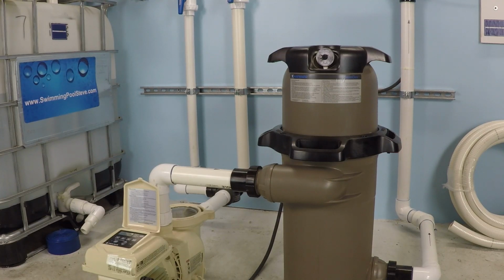When you are shopping for a new swimming pool pump, one of the most important things, probably the most important thing you need to look at in terms of your existing swimming pool installation is your filter. Your filter most likely is the largest flow restriction in your pool system. Specifically, what you need to note is the maximum design flow rate that your filter is made to handle. This is going to be very important when you choose your new pool pump.